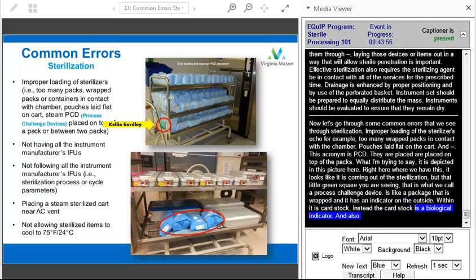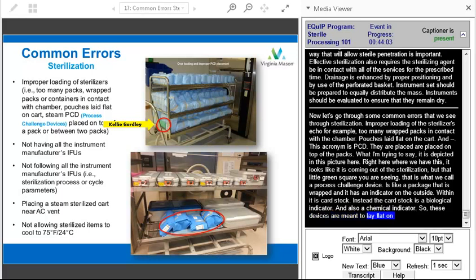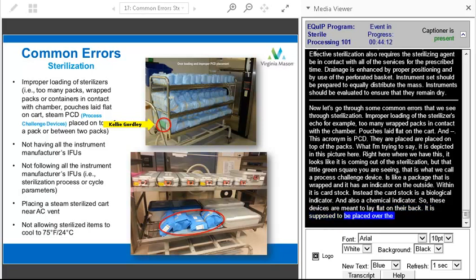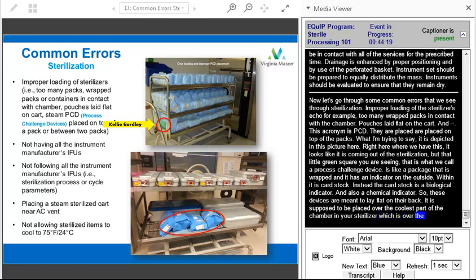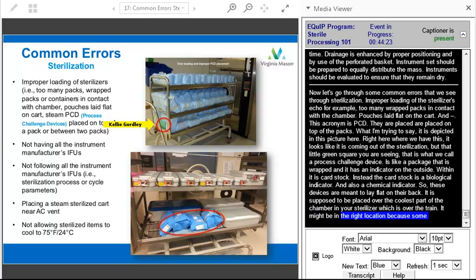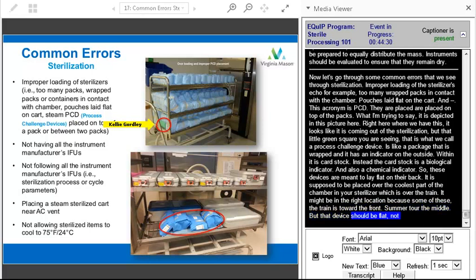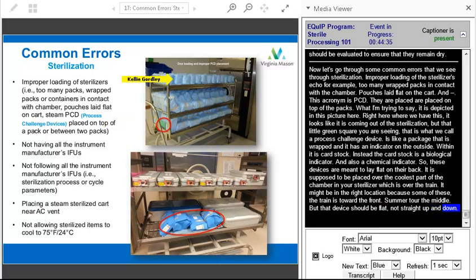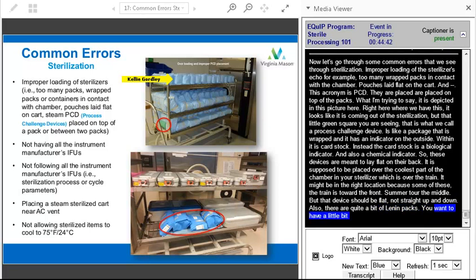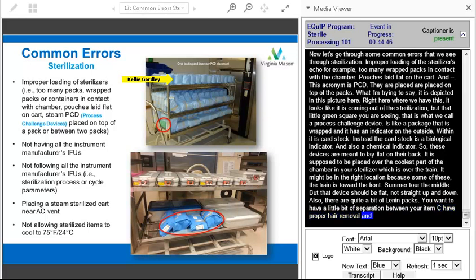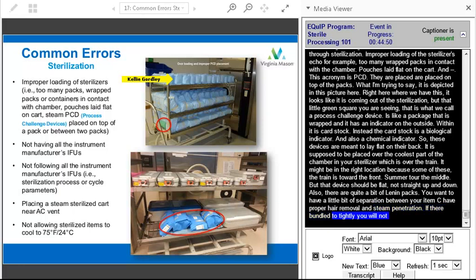These devices are meant to lay flat on their back and not be straight up like shown in this picture. And it's supposed to be placed over the coolest part of the chamber in your sterilizer, which is over the drain. Some of these sterilizers have the drain toward the front, some toward the middle, depending on where the drain is located. But that device should be flat, not straight up and down. Also, if there are quite a few linen packs, you want a little bit of separation between your items so that you have proper air removal and steam penetration. If your linen packs are bundled too compact and tight, you're not going to get that steam penetration and proper air removal if you have a pre-vacuum sterilizer.